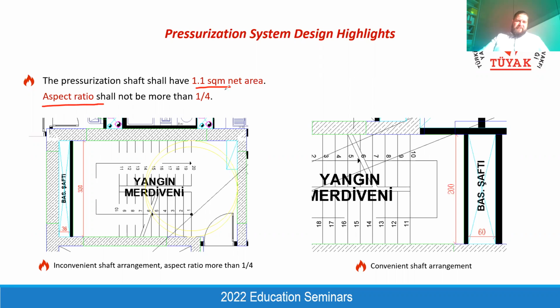And the aspect ratio, meaning the ratio between the length and the width of the shaft, should be not more than 1 to 4. It means if you have a dimension of A here, the other should be a maximum of 4A. Otherwise, this shaft does not work, for the same cause. An aspect ratio of more than 1 to 4 causes higher pressure loss, and all of the design is changed accordingly. For example, you can see an inconvenient shaft here because the aspect ratio exceeds 1 to 4. That's why it will not work as required. And here you can see a convenient shaft arrangement. The aspect ratio is okay, and the required shaft area is fulfilled. It will work as required.